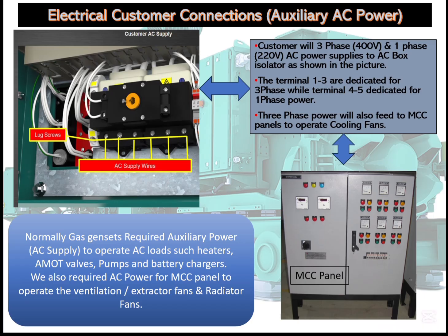On those fans, we also need AC power. So it's the customer's responsibility to provide that AC power to run the fans on the cooling tower or cooling radiator. Then if our engine is on standby, we need to run heating elements that maintain the temperature at 55 to 60 degrees centigrade for quick start. This is the auxiliary power.